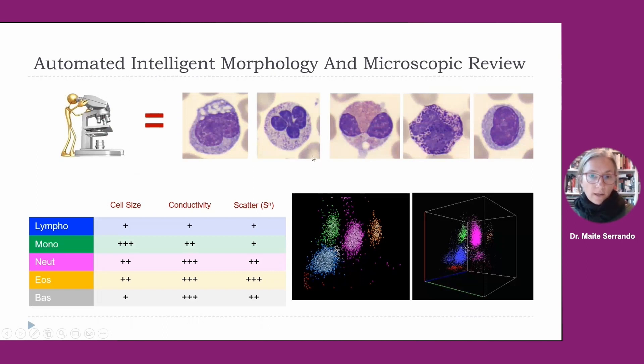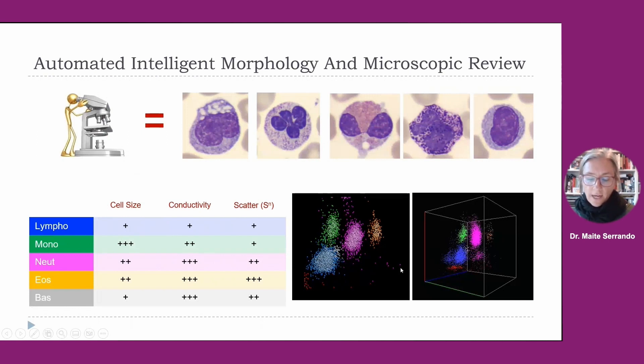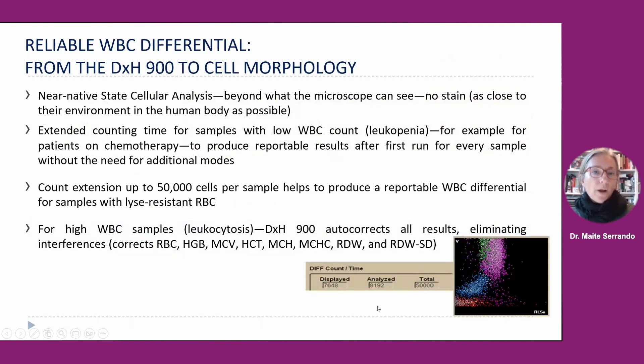Microscopically, when reviewing slides under the microscope, we can identify and describe cells, while with the automated intelligent morphology module we can classify cells into different clusters using these three parameters. Using this information, the system produces a data plot displaying a visual representation of the differential leukocyte, with volume plotted on the y-axis and rotated light scatter plotted on the x-axis. This gives us reliable white blood cell differential results from the DXH 900.